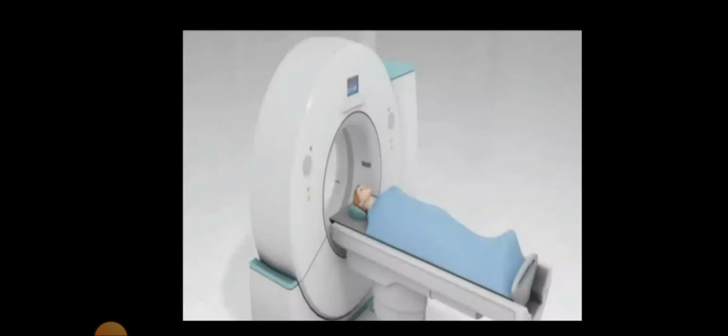And when we see the basic principle, CT scanners use the X-rays to produce the sectional or slice image, as in conventional tomography. But radiologist film is replaced by sensitive detectors. That is the difference. X-rays are used to produce the image, but the film is replaced by sensitive detectors. So the detectors measure the intensity of the X-ray beam emerging from the patient and convert this to digital data. This data is stored and it can be manipulated by a computer. That is what is happening in CT.